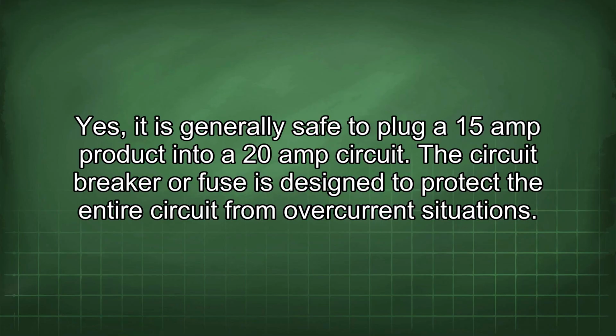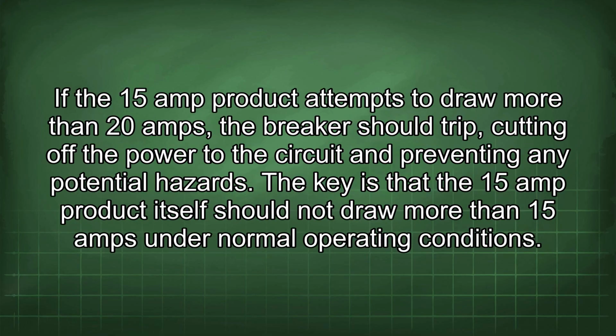Yes, it is generally safe to plug a 15 amp product into a 20 amp circuit. The circuit breaker or fuse is designed to protect the entire circuit from overcurrent situations. If the 15 amp product attempts to draw more than 20 amps, the breaker should trip, cutting off the power to the circuit and preventing any potential hazards.